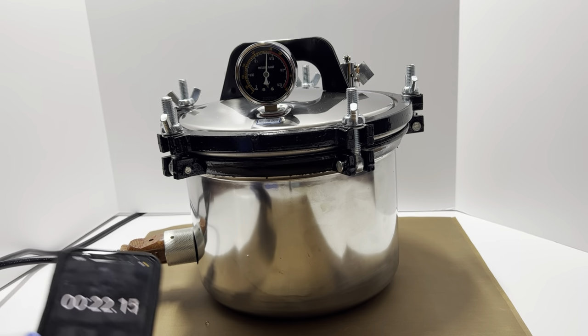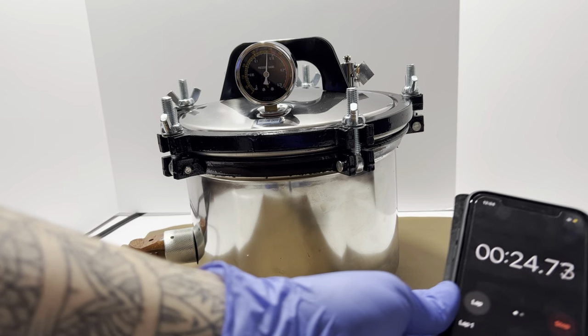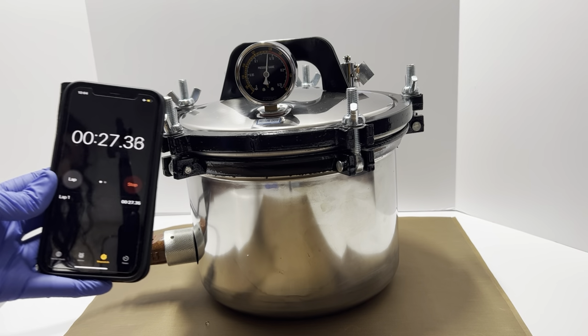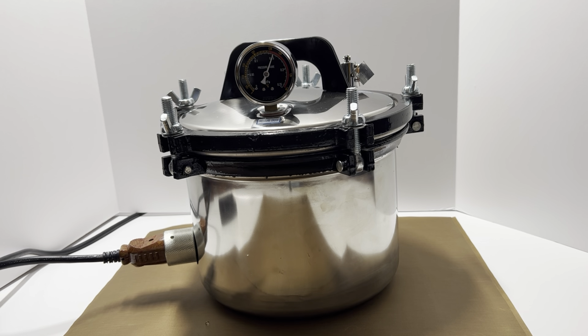So I can't leave it in the frame because I don't want to have the phone around a heat source this hot. So I'll come back from time to time and I'll just put it in the frame here. Once it reaches the desired temperatures and pressures, we're gonna see the valve over here off to the right start pushing the steam out. And I believe this is the first of those motions. You can hear the unit working. So we're only a minute and 34 seconds into the sterilization process. And that's the pressure valve releasing pressure.